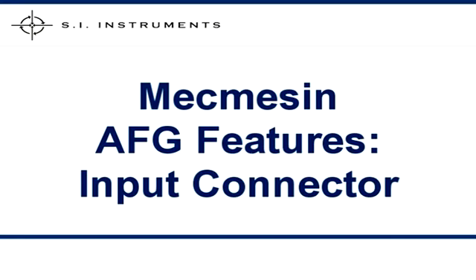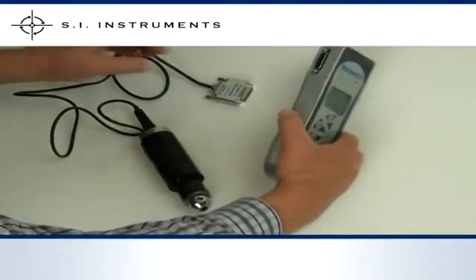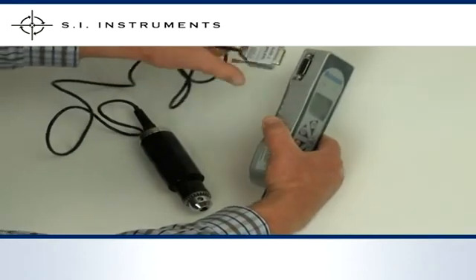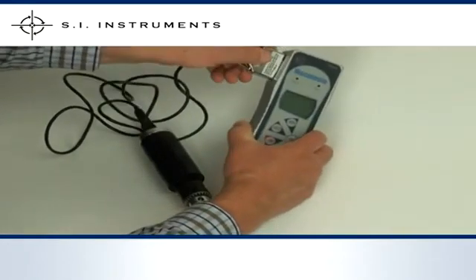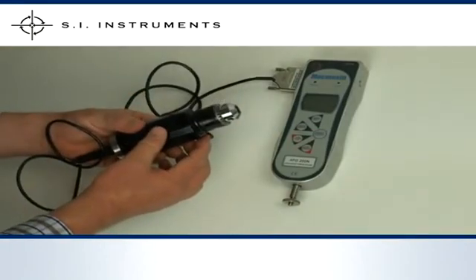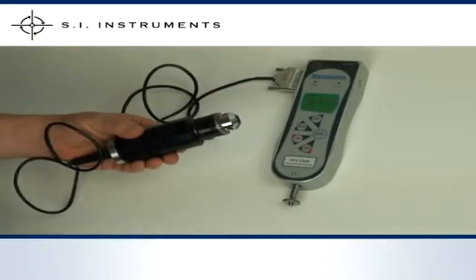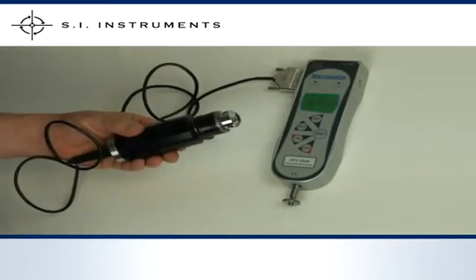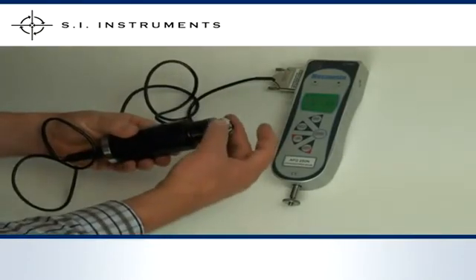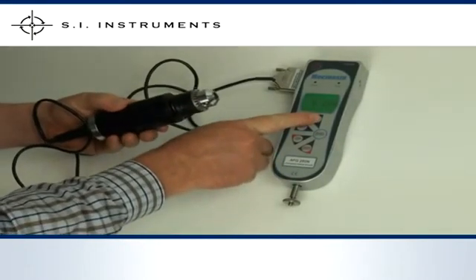The Mecmesin Advanced Force Gauge is also fitted with an input connector for external force and torque transducers. Here we have a Mecmesin Torque Screwdriver 10Nm. All we need to do is connect the torque screwdriver to the input connector and turn the gauge on. The gauge will recognise the transducer and its capacity during start up and adopt the correct calibration settings. There is no need for telling the electronics what is connected, with the unit now immediately ready for action.